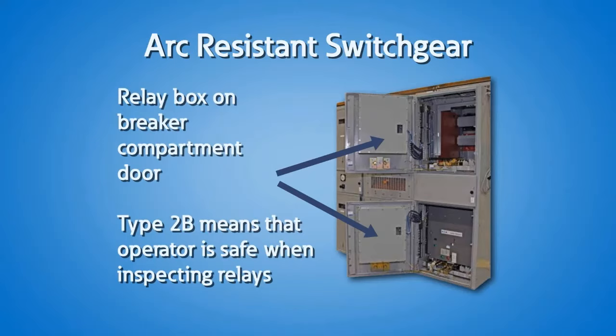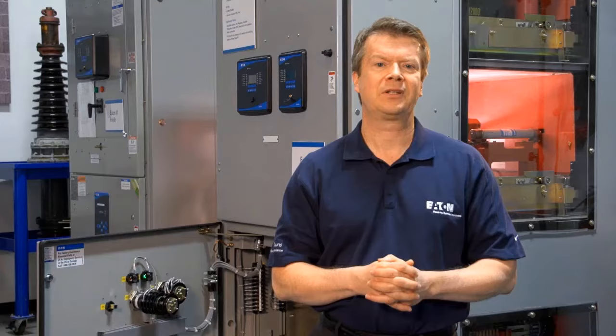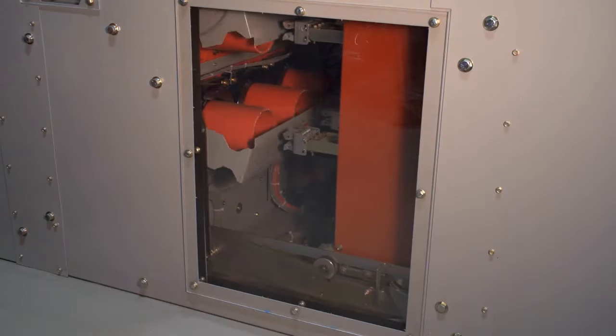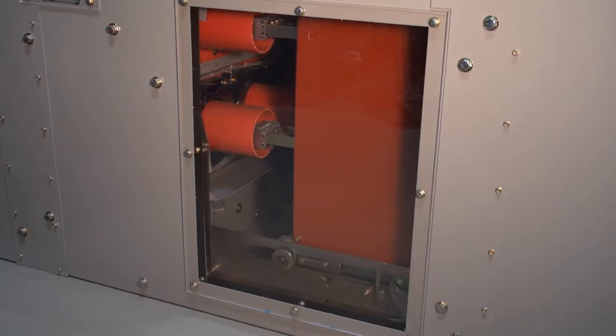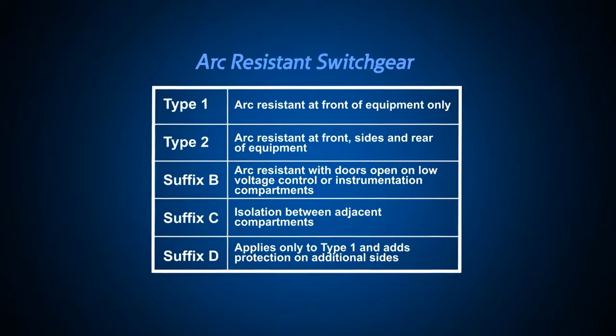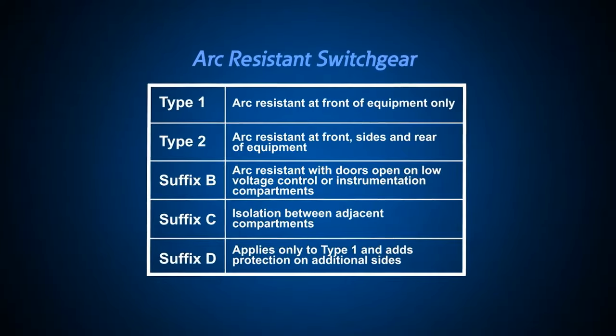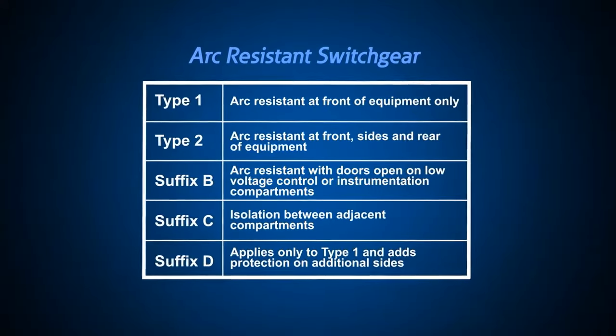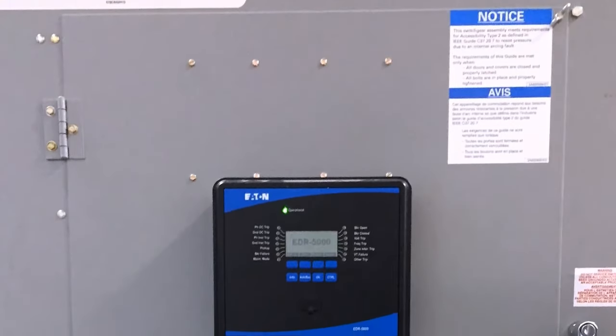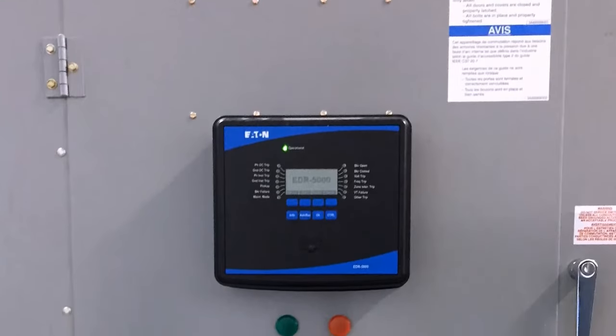For example, this gear is designed to do everything with the door shut, like this self-racking mechanism in our medium voltage arc resistant switchgear. The most common type of arc resistant switchgear is type 2B. With 2B medium voltage arc resistant gear, the low voltage metering, relaying, and control compartments are isolated from the gear with a separate door.